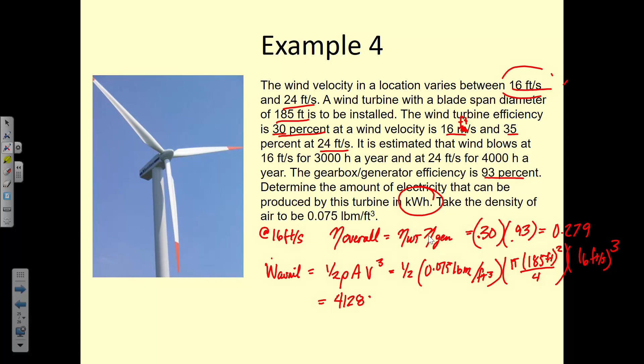Then from there, we're going to look at our available power, which is equal to 1/2 times the density times the area times the velocity cubed, which is 1/2 times 0.075 pound mass per feet cubed for density, pi times 185 feet squared over 4, and multiply by 16 feet per second cubed. So we find an available work of 4128806, and the units on that are pound mass feet squared per second cubed.